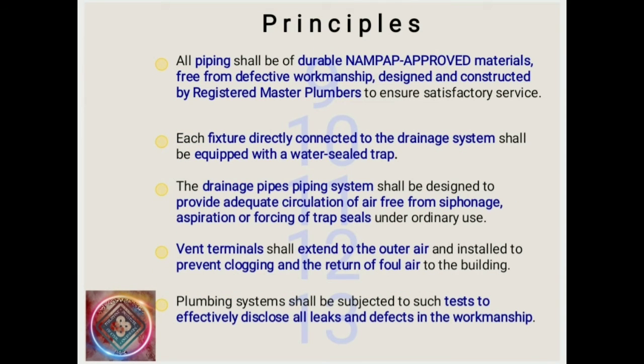Ninth: All piping shall be of durable, approved materials, free from defective workmanship, designed and constructed by registered master plumbers to ensure satisfactory service. Tenth: Each fixture directly connected to the drainage system shall be equipped with a water-sealed trap. Eleventh: The drainage piping system shall be designed to provide adequate circulation of air, free from siphonage, aspiration, or forcing of trap seals under ordinary use.